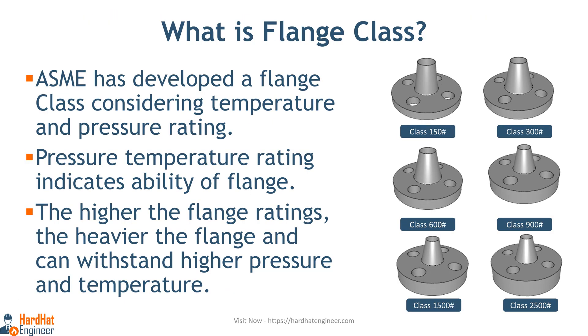Flange class refers to the pressure-temperature rating of a flange. In simple terms, it tells you the maximum pressure and temperature that the flange can handle under specific operating conditions. Flange classes are typically represented by numerical values such as 150, 300, 600, 900, 1500, or 2500. These numbers indicate the flange pressure rating in pounds per square inch. The higher the class number, the higher the pressure the flange can withstand, due to a heavier flange body, as you can see here in the image.